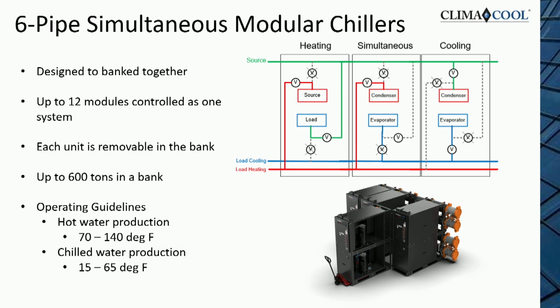And so I think from a troubleshooting, from an industry perspective, it's a highly efficient system. It's friendly to service. It's easy from a manufacturing standpoint, and so it may not be as fancy as some of the other products that were discussed, but I think it is a nice solution. And then just some of the guidelines. Typically, this product is 70 to 140 degree leaving water. Most of these systems are 454B, and then 15 to 65 degree on the chilled water side. And with that, I'll hand it off to Dan.